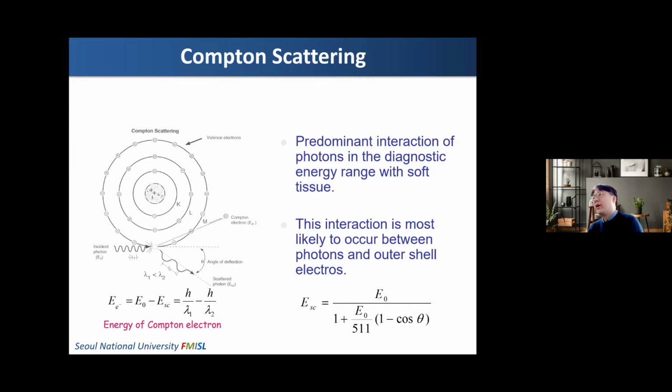But unfortunately, radiation measurement systems don't have a sufficiently good energy resolution. So that is why it is impossible to totally eliminate the scattered photons only based on the energy information. So we perform some additional scatter correction, a method to remove the remaining scattered photons after applying the energy window around the primary photon.